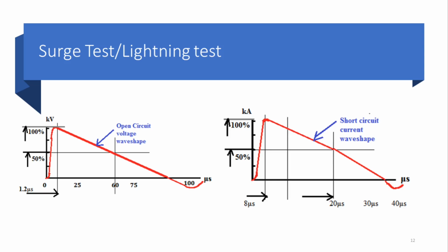The figure on the left shows the standard waveform for the test standard EN 61000-4-5 surge test, which is a single unidirectional impulse specified by two waveforms at the same time: a 1.2 by 50 microsecond voltage impulse into an open circuit, and an 8 by 20 microsecond impulse into a short circuit, leading to its common name, the combination wave.